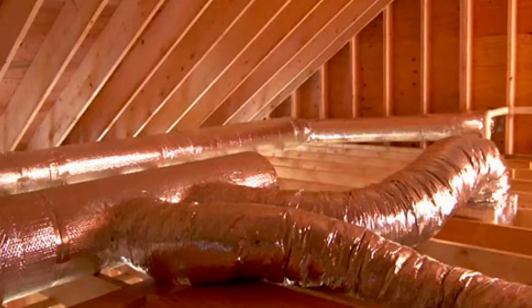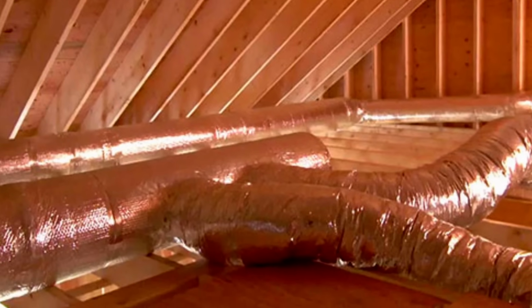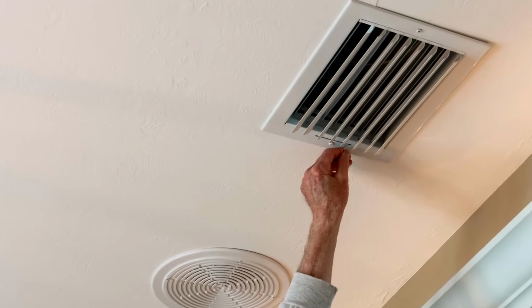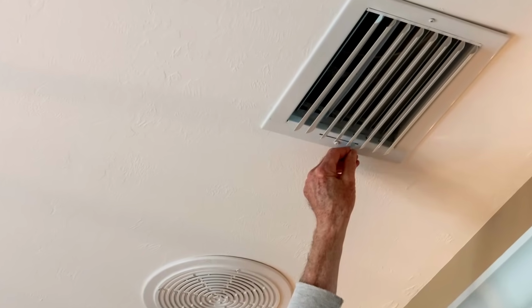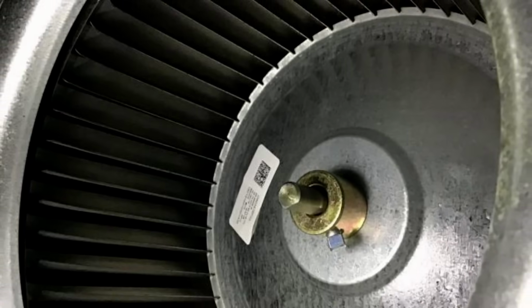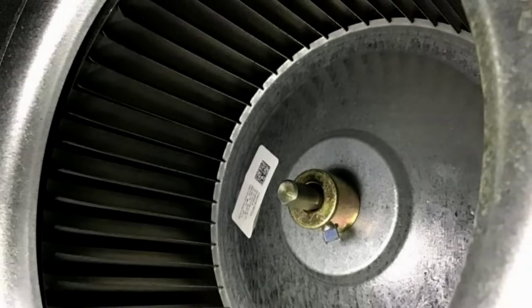The ductwork was originally sized to move a certain amount of air. When you start closing vents, especially closing them entirely, it's almost like you've added a damper to that space, pushing more air to other spaces. In reality, you have a blower motor trying to push a certain amount of air through a much smaller space.